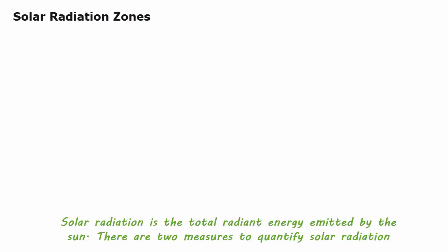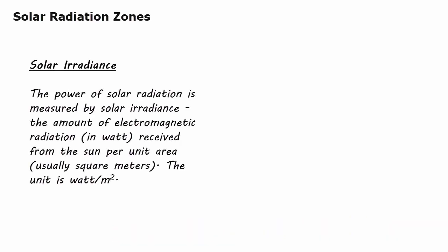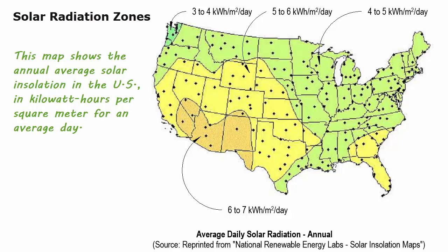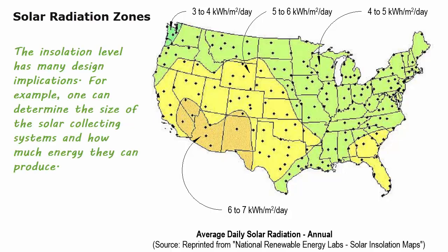Solar radiation is the total radiant energy emitted by the sun, and there are two measures to quantify it. Solar irradiance measures the power of solar radiation — the amount of electromagnetic radiation received from the sun per unit area — with units of watts per meter squared. When solar radiation is accumulated over time, it is called solar insolation, a cumulative energy measured over a period of time per unit area, with units of watt-hours per meter squared. A map showing annual average solar insolation in the U.S. in kilowatt-hours per meter squared for an average day illustrates design implications, such as determining the size of solar collecting systems and how much energy they can produce.